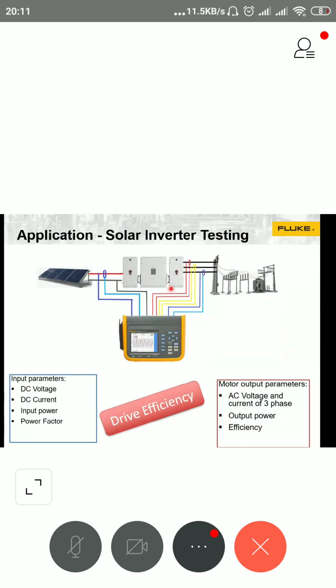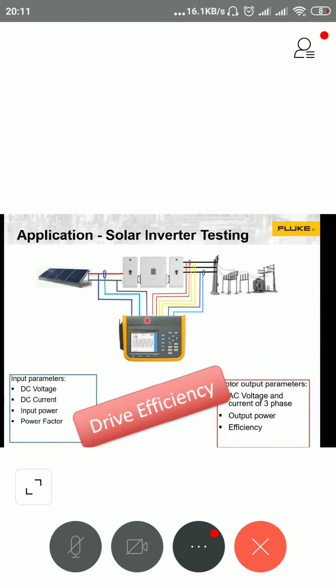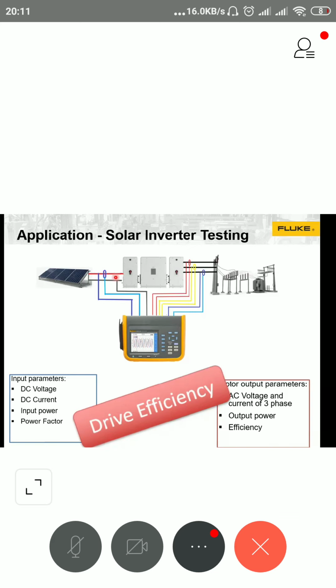Today, Fluke has come up with a unique solution where, with a single equipment, because of the channel isolation, you can connect the DC input as well as the AC output, measure the input and output, and directly calculate the efficiency. The instrument shows the drive efficiency on a single screen. And not only that, since today the solar DC input voltage has crossed more than 1000 volts, Fluke is also providing a solution up to 1500 volts DC.